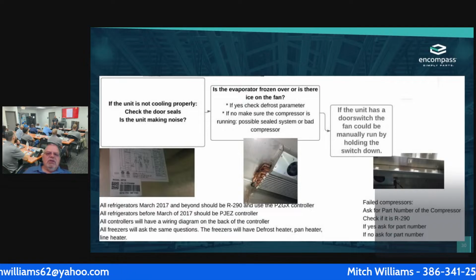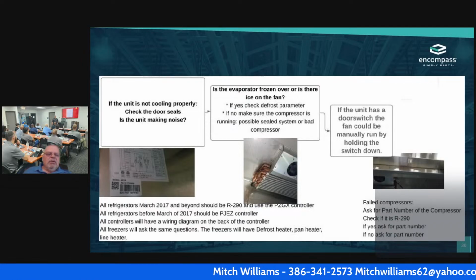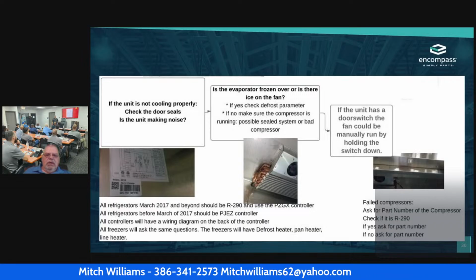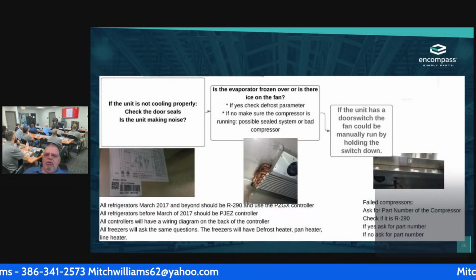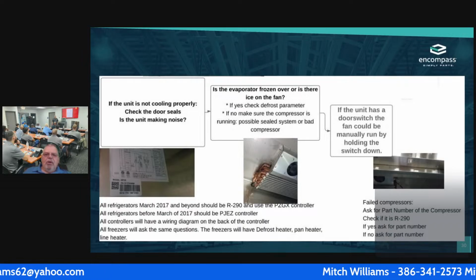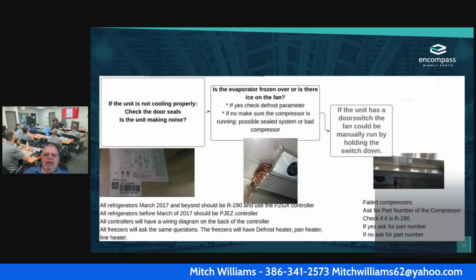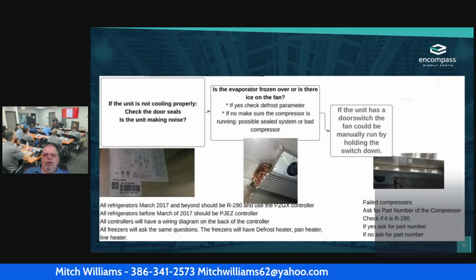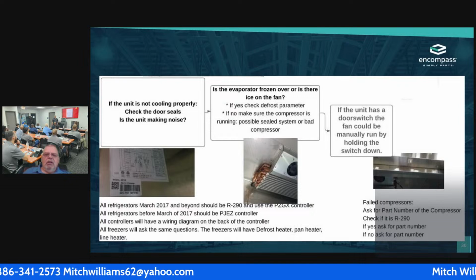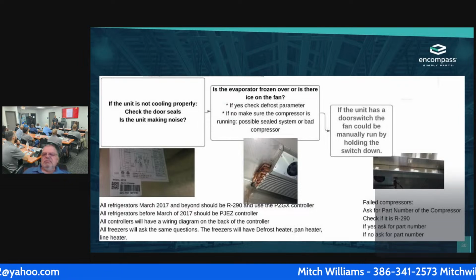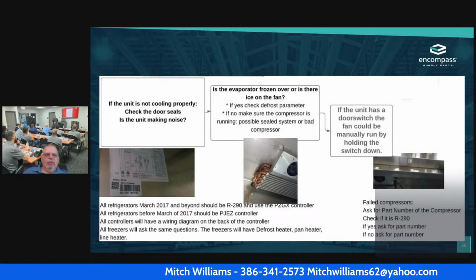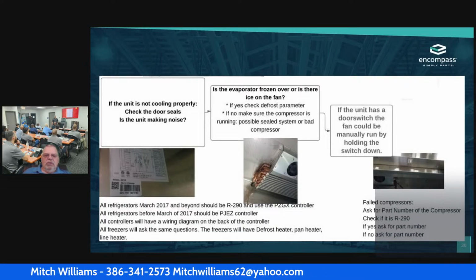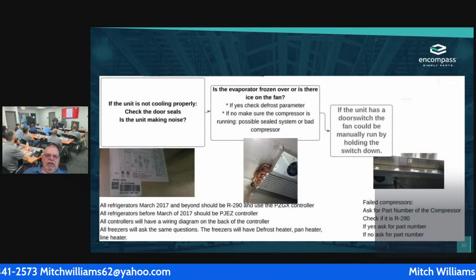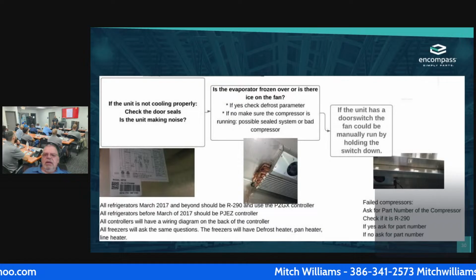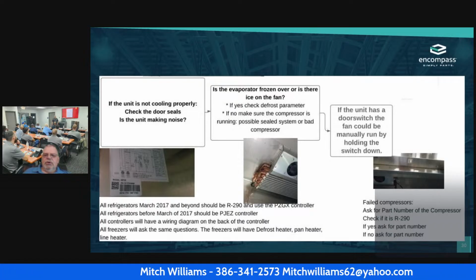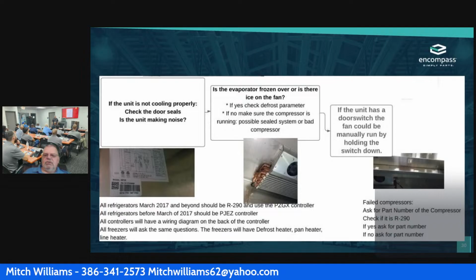Okay. If the unit is not cooling properly, number one, I'm going to check the door seals. Okay. Is the unit making noise? These are all the flow charts for this. Okay. If the evaporator is frozen over or ice on the fan, if yes, check your defrost parameters. If no, make sure that the compressor is running, possibly a sealed system or a bad compressor. Okay, we're going to get a little bit farther down, and we're going to hit all this. I touch on it down here at the very bottom. Okay, if the unit has a door switch, the fan could be manually run by holding the switch down.